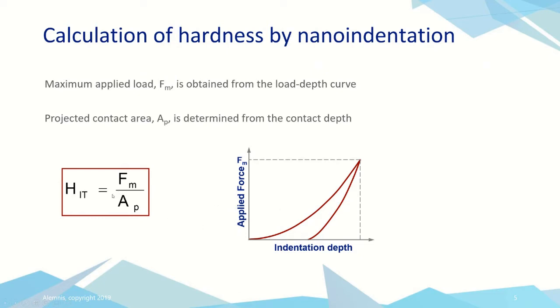And the contact area, AP, or the projected contact area in this theory, is taken directly from the calibration of our indenter shape. Typically, we might be using a three-sided pyramid, a Berkovich-shaped indenter, and so we know the area at every depth that it might be used at, and we use that calibration curve to understand what is AP at the contact depth that we're using. So a simple equation will give us HIT, which is the hardness. IT shows that it's by instrumented indentation per the ISO 14577 standard.